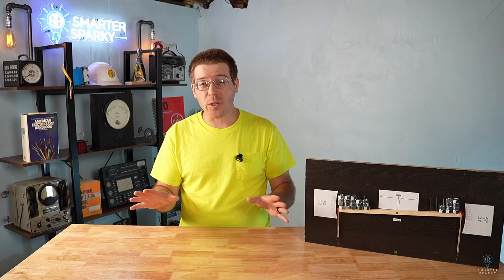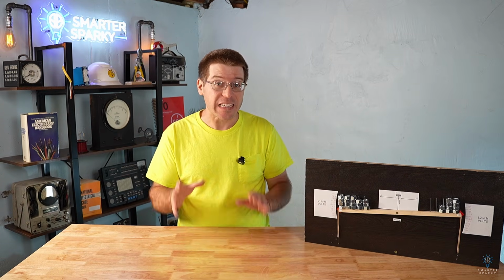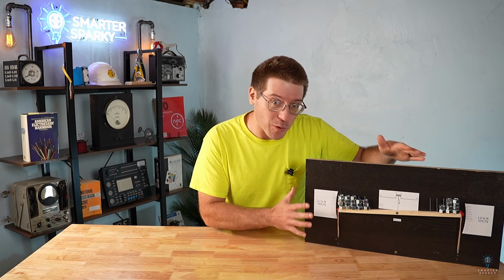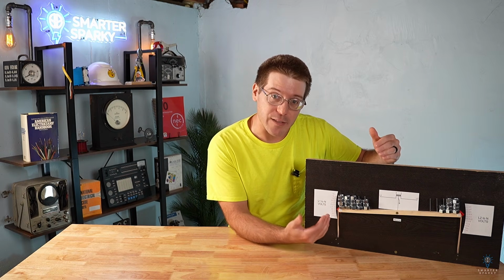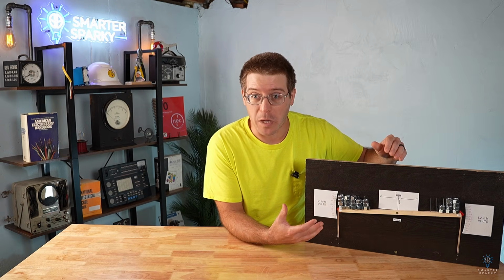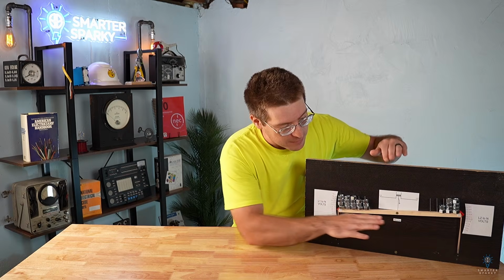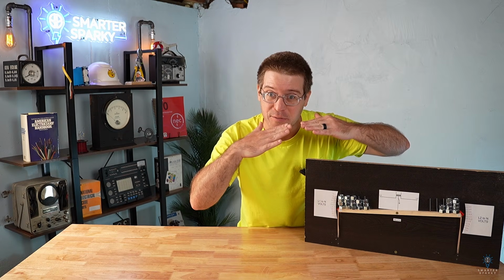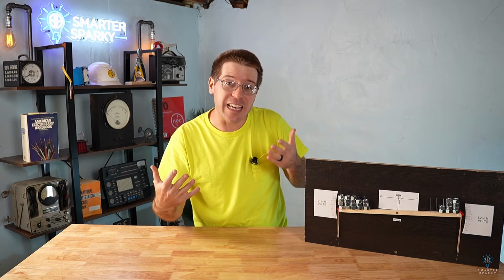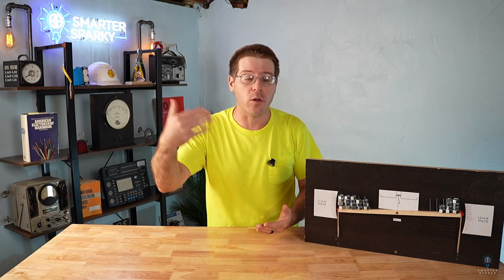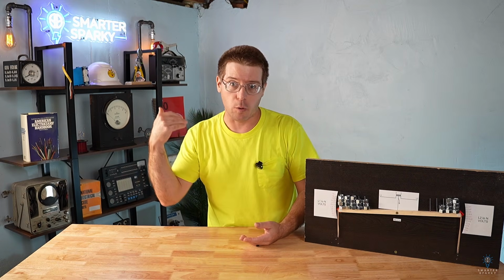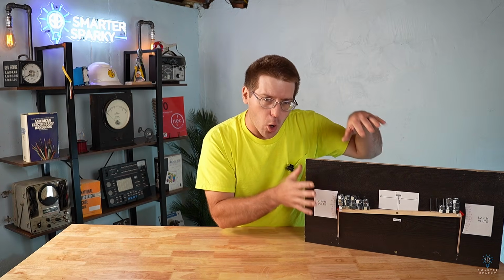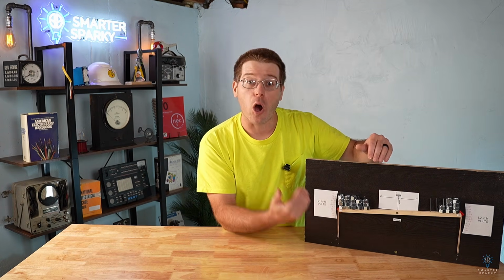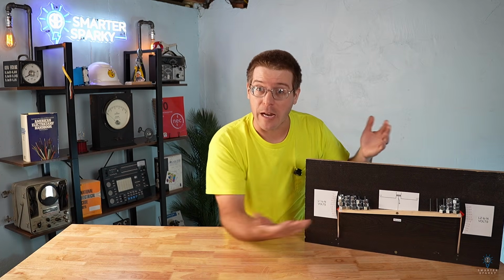Voltage drop is totally normal and naturally occurs, even in a perfectly operating electrical system. This demonstration was just a rough analogy. If we wanted to visualize real world voltage drop as well, the normal stuff, this beam itself should actually have a tiny bit of flex to it as well. That would take into account the actual normal voltage drop out on a branch circuit or on the actual conductors that go out to loads. In this case, we were only focusing on the voltage drop caused by that loose center point, that neutral connection.